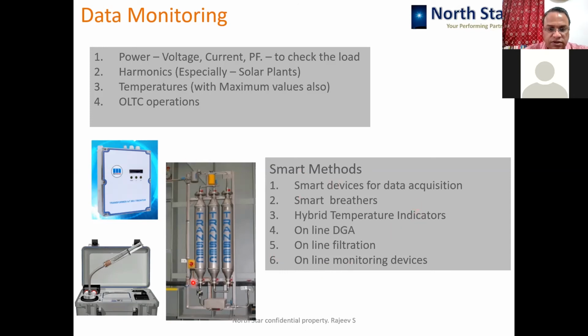Online filtration, this is Transec. We deal in this device. We are authorized representative for this. So Transec is the device which filters the oil online without any disturbance to your continuity of the service, without any need of taking the shutdown, and preventing and protecting your production loss because you are not switching off the transformer, and it keeps on absorbing the moisture from the oil and also from the solid insulation because it breaks that thermal equilibrium condition which doesn't happen in case of routine oil filtration. So this is again a very smart device as far as the oil filtration is concerned.